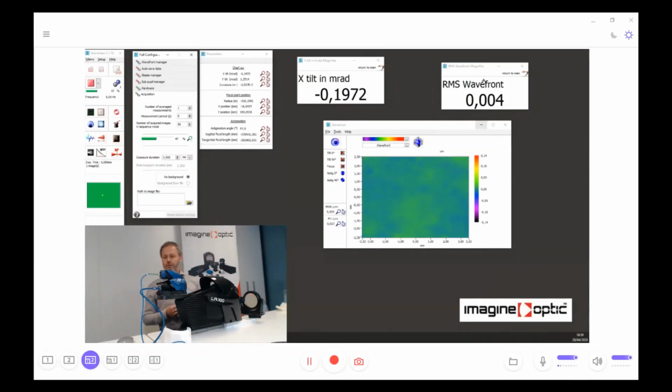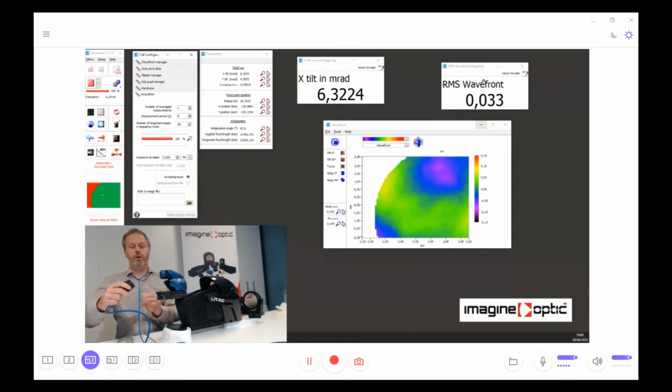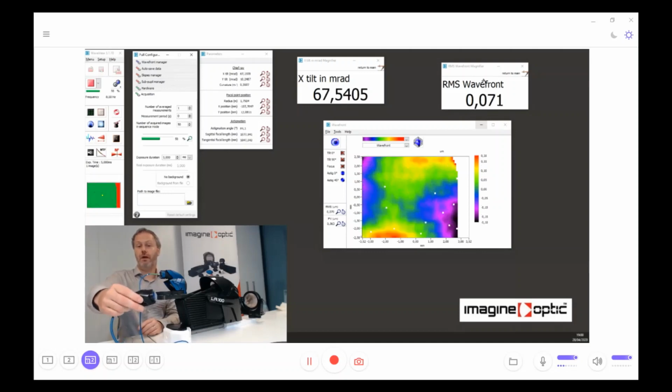I want to conclude this demo by showing you something interesting now. And this will be my last thing. As you probably already saw, in this device there is a Shack-Hartmann wavefront sensor, and I can very quickly remove only the wavefront sensor from the R-FLEX tube and use it as a wavefront sensor, for instance, to measure a laser, to measure something else.